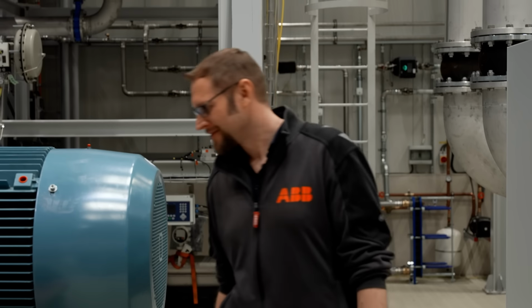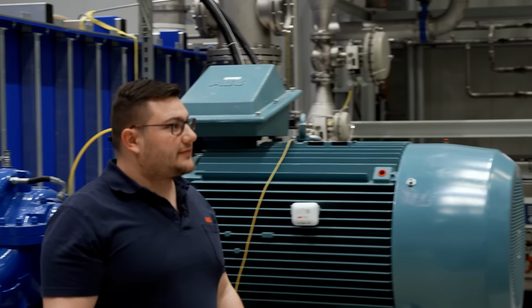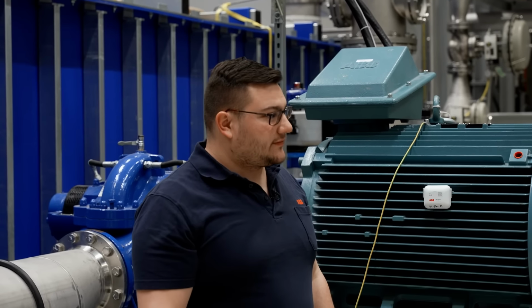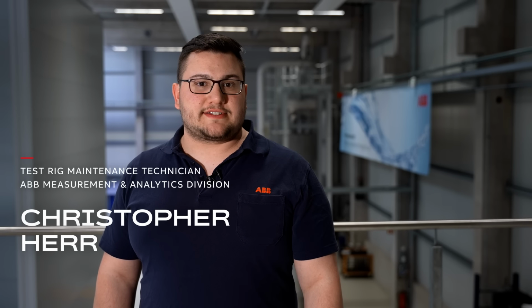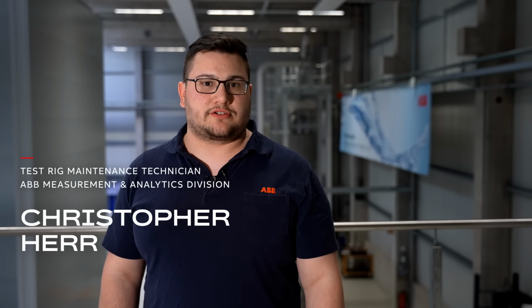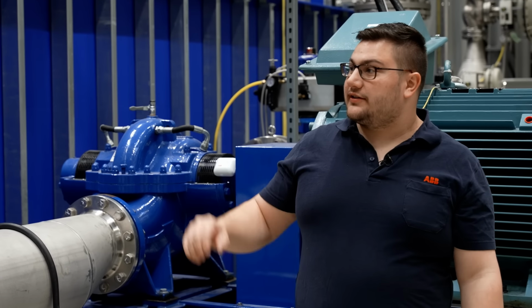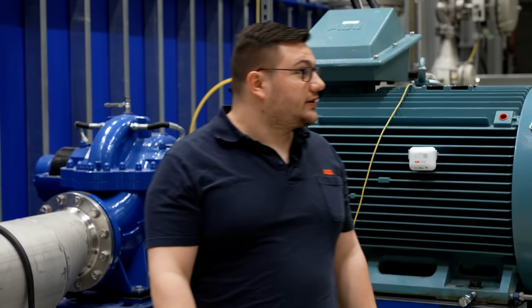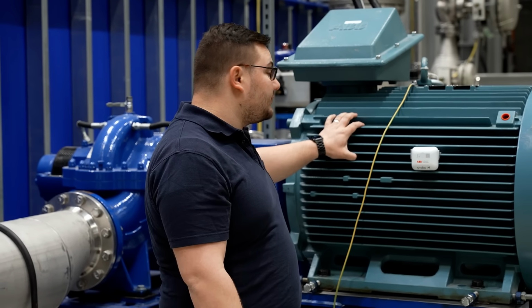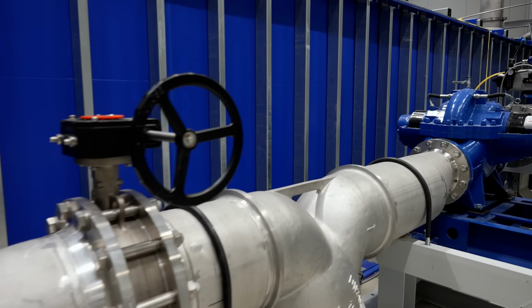Hi Christopher. Hi. Can you just tell us something about the technique of the pump and the water tank? Hi, my name is Christopher. I'm working for ABB for around 6.5 years now, and I'm in the calibration section for the last 2.5 years. My job here is the maintenance of the calibration rigs, repairing cables, changing valves, and basically everything that happens around here. So here we have our water tank, which contains 150 cubic meters of water. And here we have our big pump, which allows us to fill a bathtub in a second.